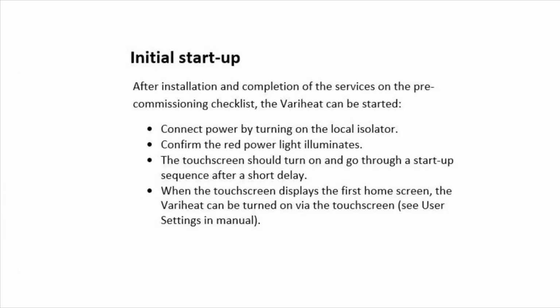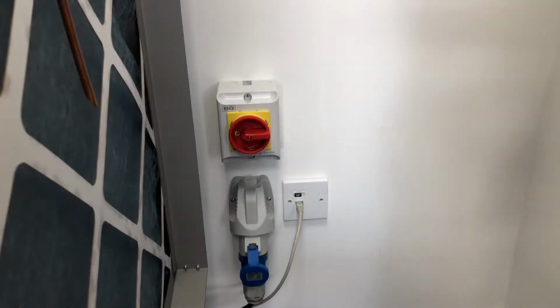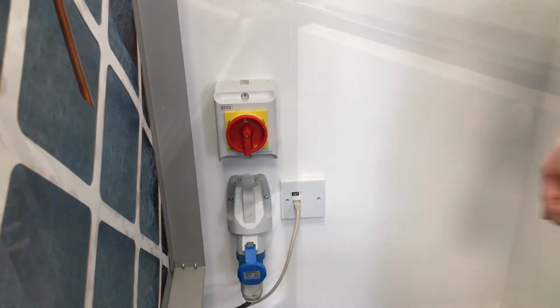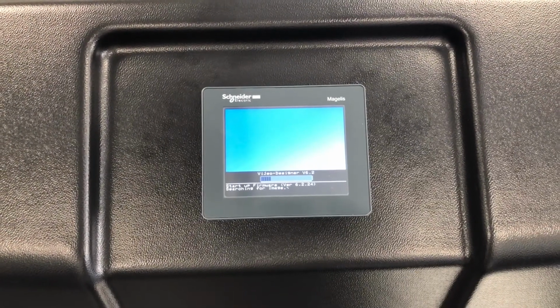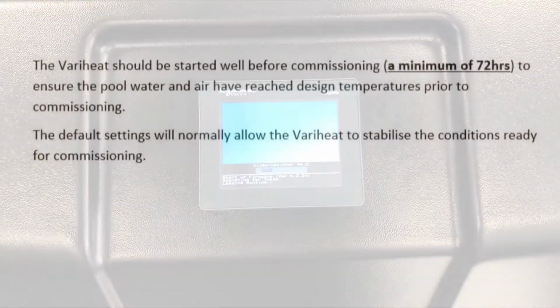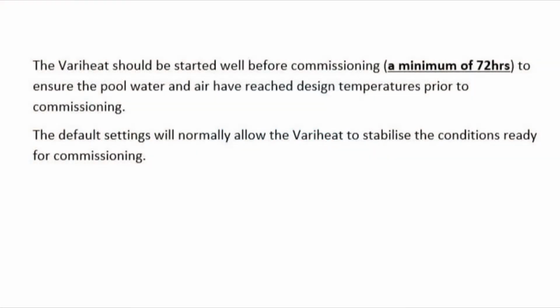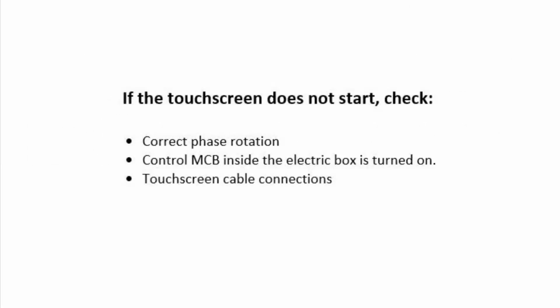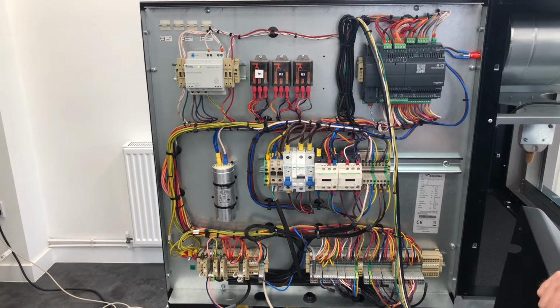The installer should also switch on the AHU prior to attendance following the initial startup procedure as demonstrated. Startup should be carried out a minimum of 72 hours prior to commissioning to ensure air and water temperatures and humidity conditions stabilise. If the touchscreen fails to start, check the phase rotation, miniature circuit breaker and the touchscreen cable connections as demonstrated.